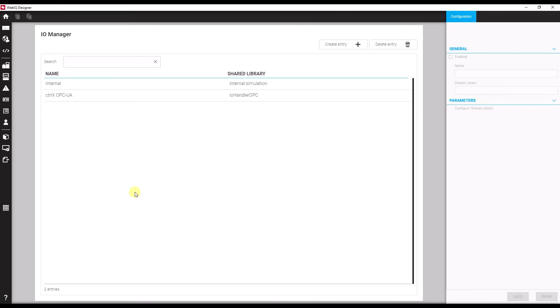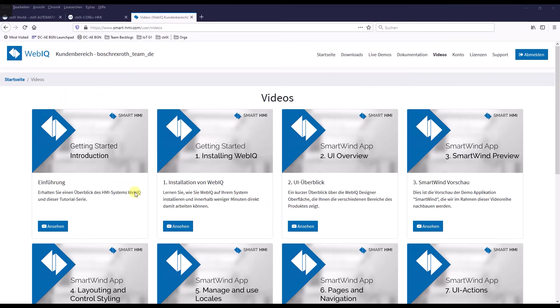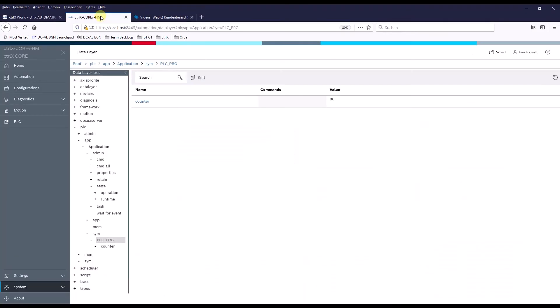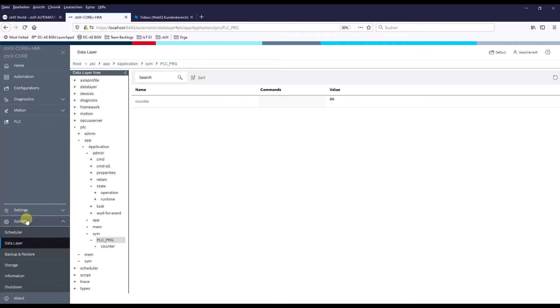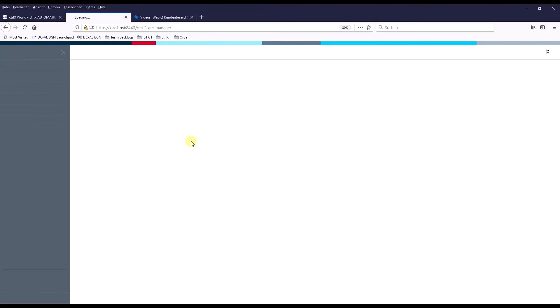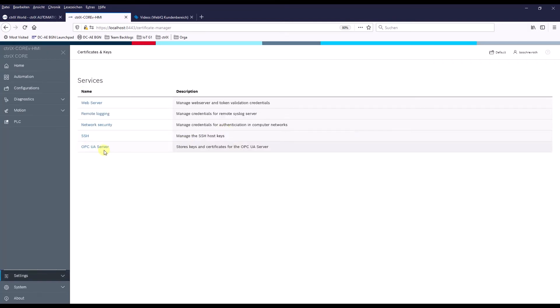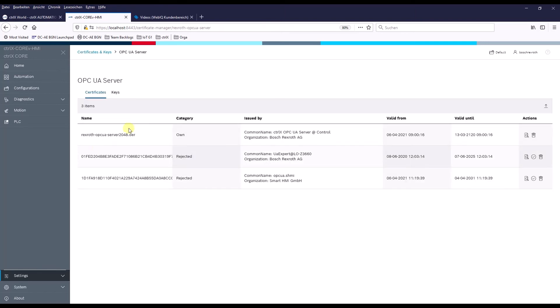To allow WebIQ to talk to our OPC UA server, we need to trust the application in our system. That means you have to jump back to the ctrlX and go to Certificates and Keys. There, for the OPC UA server, we have a separate slot. Now we see that the WebIQ server tried to talk to our OPC UA server, and we have to trust the certificate one time. In subsequent starts, the WebIQ app will be considered a trusted app, so there won't be any restrictions in further communications between the OPC UA server and WebIQ.